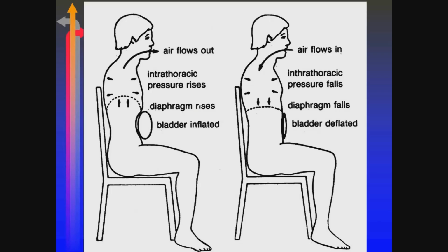As that bladder inflates, it pushes the diaphragm up, and the patient exhales. Relaxes, and the patient inhales. So it's opposite of a negative pressure ventilator. When that bladder's inflating, it actually is forcing air out, and it passively is allowed to go back in. With these kinds of things, we're not talking about somebody who needs full support. Obviously, they just need some assist on their breathing.